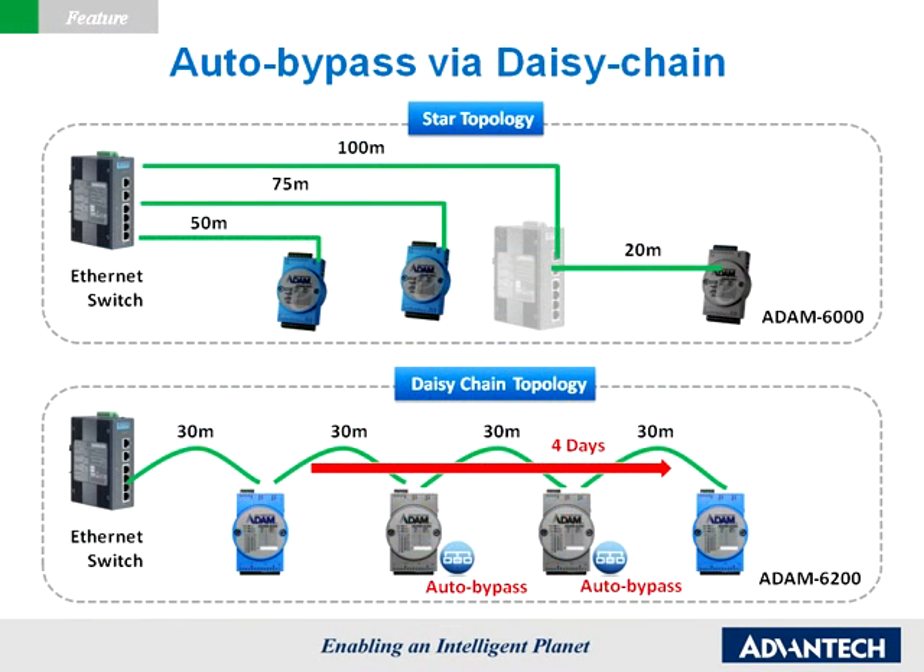Every ADAM-6200 module accommodates two LAN ports with a built-in switch for daisy-chain connection. Daisy-chaining allows for flexible module deployment without the need for an external Ethernet switch. However, if a module in the daisy-chain network is damaged, downstream modules and Ethernet devices will be affected.